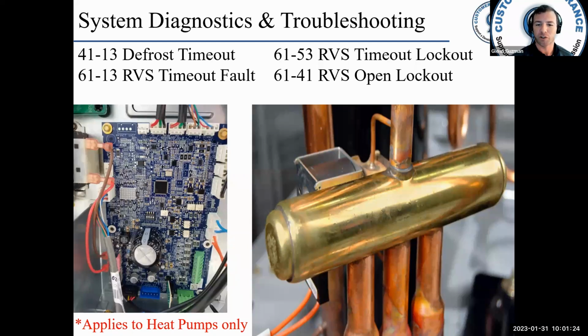Defrost timeout, which means your defrost took too long and you did not bring the coil temperature up above the threshold. It's going to go back into heating, but you're going to get the 4113 and it's going to tell you, hey, we defrosted and we didn't do our job. So it's just alerting you to what's happening. If that happens, causes could be extreme ice on the outdoor coil, probably pretty rare in our area. Coil temperature sensor not properly attached, probably something that's more likely, or the coil sensor is reading incorrectly, possibly.